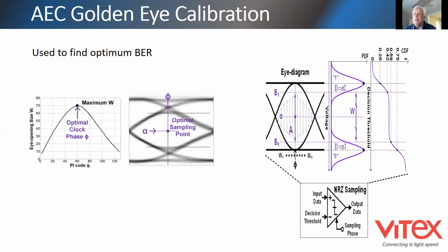If that separation or voltage changes to a certain extent, that decision threshold will assert, looking at a change in the phase angle. And the way we do that is almost through a lookup chart for environmental data, because we find that most of the shifts that we get are through environmental data, mostly temperature.